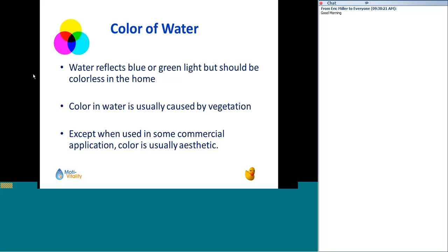What you do is you test your water. Let's say you test the water and you've got 2 parts per million of iron, and the water has a yellowish tint to it. Now we need to determine whether any of that's oxidized iron in the water. The way we do that is we run your raw water through your mini water softener. Now you recheck for iron again. Let's say you still have almost a part per million of iron in the water after the water softener.